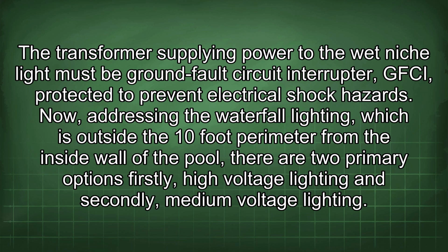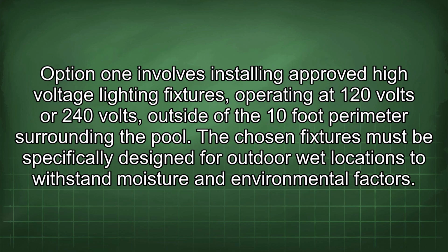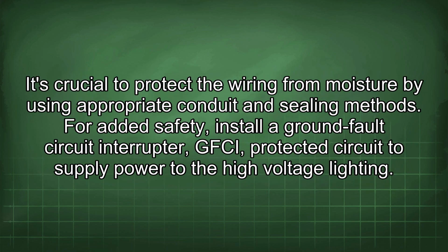shock hazards. Now, addressing the waterfall lighting, which is outside the 10-foot perimeter from the inside wall of the pool, there are two primary options: firstly, high voltage lighting, and secondly, low voltage lighting. Option 1 involves installing approved high voltage lighting fixtures operating at 120 volts or 240 volts outside of the 10-foot perimeter surrounding the pool. The chosen fixtures must be specifically designed for outdoor wet locations to withstand moisture and environmental factors. It's crucial to protect the wiring from moisture by using appropriate conduit and sealing methods.